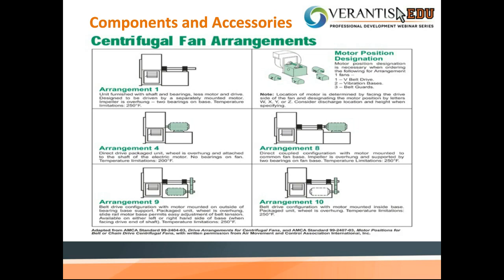So next to that, you'll see the motor positions, everything from a W arrangement all the way up to a Z. Basically, the shaft and the pulley are going to be in line with the motor. The shaft of the fan and the motor shaft are going to be in line. It's just a matter of where we put it within the position of the fan.